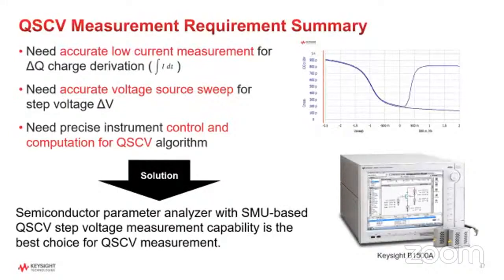What are the needs of the equipment you need to make an accurate QSCV measurement with SMUs? Well, as I mentioned, you need very good low current measurement because you're integrating the current over time, and also good time measurement capabilities to get an accurate delta Q for the measurement. You also obviously need a good, accurate voltage sweep capability for the delta V. You also need a built-in algorithm in the instrument for doing the quasi-static calculation. And we actually do have all of these capabilities in the B1500A. We can do quasi-static CV with the SMUs very easily.